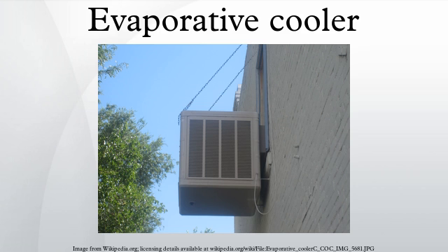Direct evaporative cooling is used to lower the temperature of air by using latent heat of evaporation, changing liquid water to water vapor. In this process, the energy in the air does not change. Warm dry air is changed to cool moist air. The heat of the outside air is used to evaporate water. The RH increases to 70 to 90%, which reduces the cooling effect of human perspiration. The moist air has to be continually released to outside or else the air becomes saturated and evaporation stops.